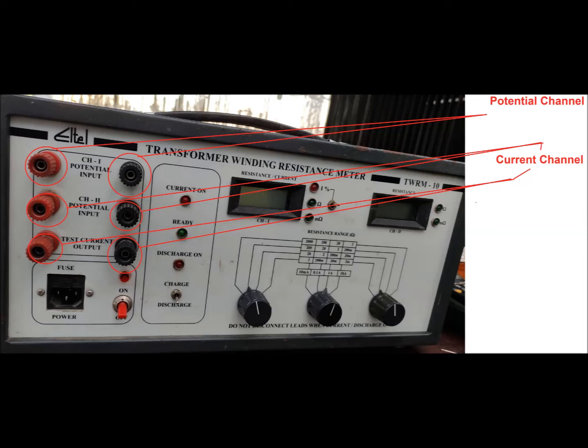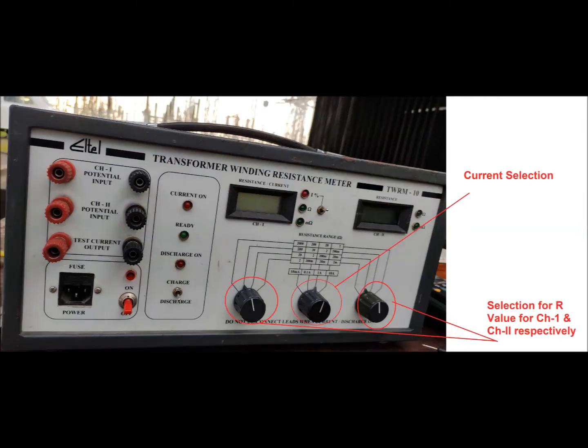In the lower right side of the diagram, there are three knobs. One is for selecting the injected current, which can be selected from 0.01 to 10 ampere, and the left and right knobs are for selecting the range of the resistance to be measured.